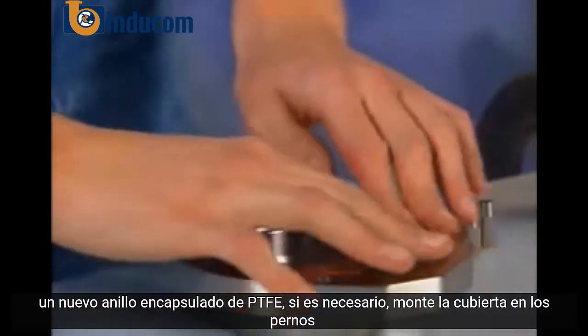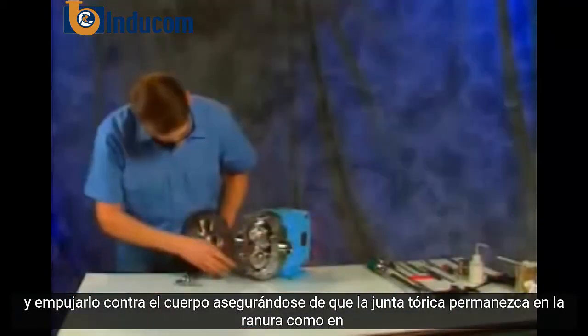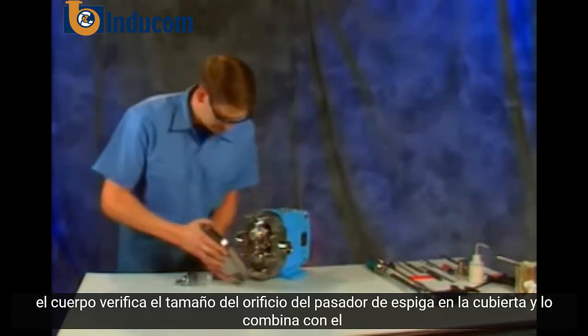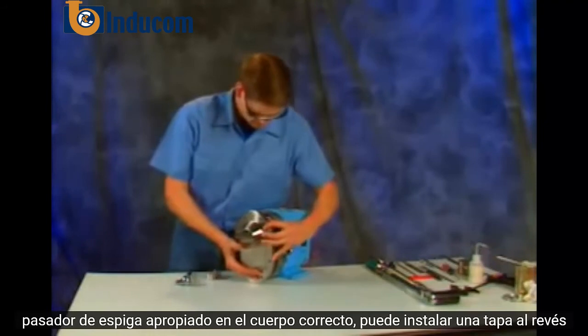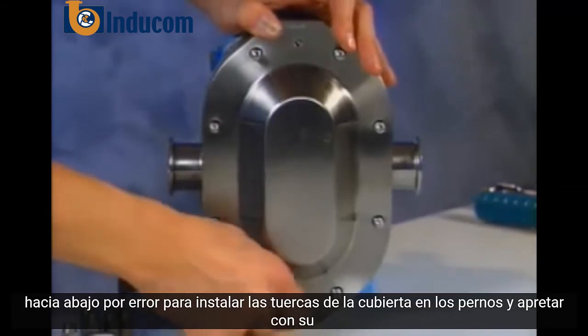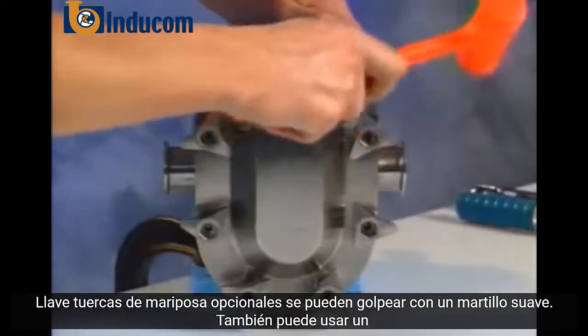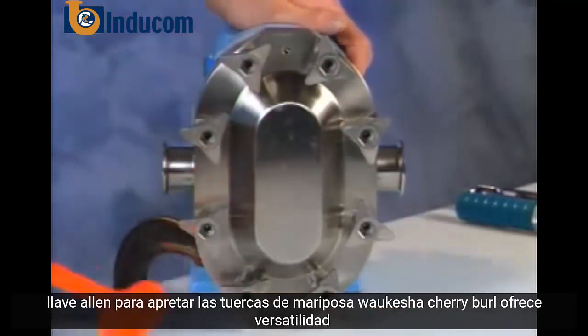Mount the cover on the studs and push it against the body, making sure the o-ring remains in the groove. Check the dowel pin hole size on the cover and match it with the appropriate dowel pin on the body — so you can't install a cover upside down by mistake. Install the cover nuts on the studs and tighten with your wrench. Optional wing nuts can be tapped with a soft hammer, or you can use an Allen wrench to tighten them.